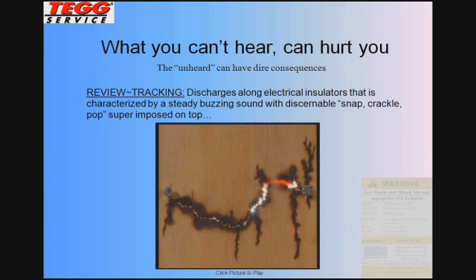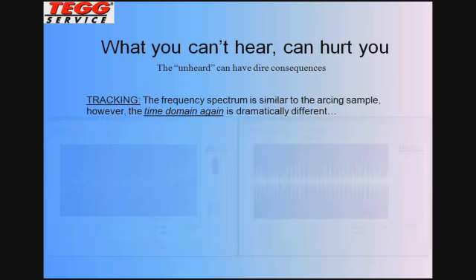With discharges along insulators, what's absent is current flow. And for infrared to be effective, you have to have thermal effects and temperature differences. And in electrical systems, that means current flow. So with tracking, you do not have that current flow, although the discharges are seeking a path to ground. They have not found that yet. So you will not see tracking with infrared. If you're fortunate, you will see the carbon trails that are left behind by these discharges, but in most cases, we're using the ultra probe prior to even opening equipment and would not have that opportunity to see those.